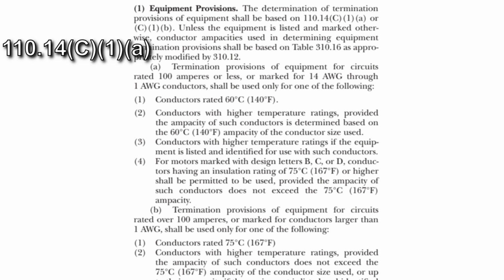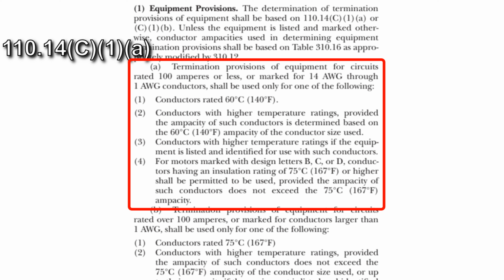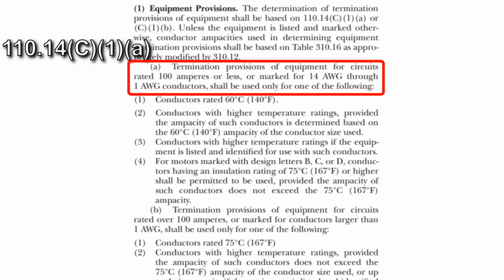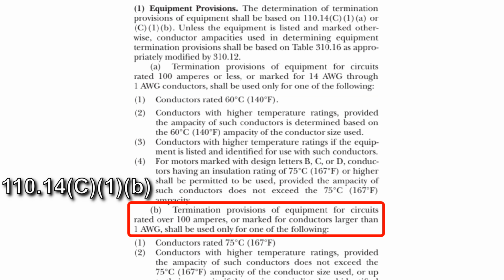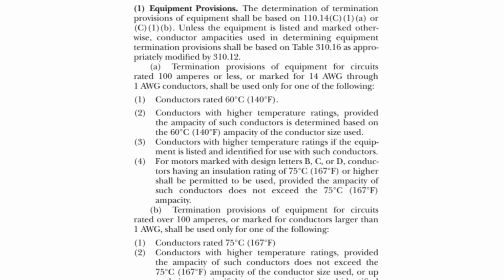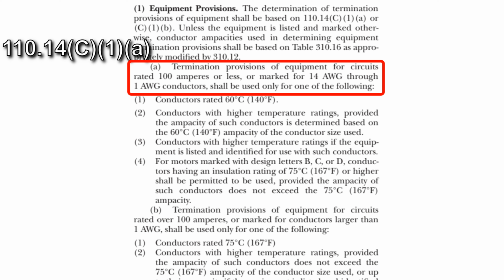I'm rattling through a lot of code here, but don't worry, it all applies to the example circuit, so it'll become more clear as we move through it. Let's see what 110.14(C)(1)(a) and (b) are all about. 110.14(C)(1)(a), termination provisions of equipment for circuits rated 100 amperes or less, or marked for 14 AWG through 1 AWG conductors, shall be used only for one of the following. Notice that (a) applies to circuits of 100 amps or less, with a maximum conductor size of 1 AWG. Now take a moment to note that (b) applies to circuits over 100 amps, with a minimum conductor size of over 1 AWG. Since we have a 100 amp circuit, we'll only be reviewing (a).